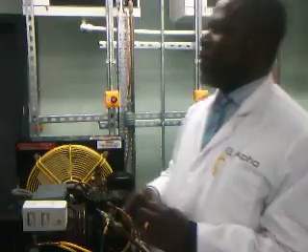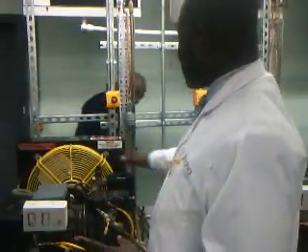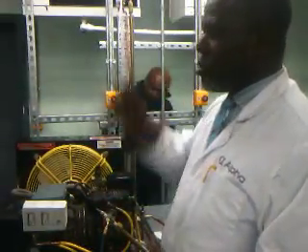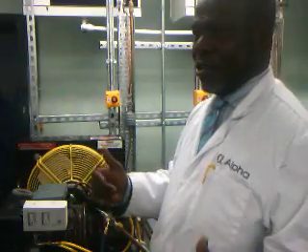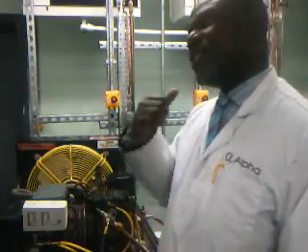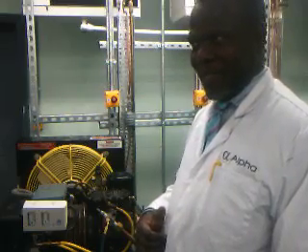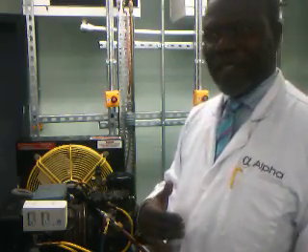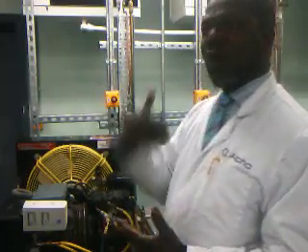You get your subcooling. You just have to know where you are. Now, if you check your subcooling and it is too low, like we said, 2 or 3, there is undercharge. What should you do? Charge the system up, just like we did for the superheat, because your condensation is low. It's not condensing properly.